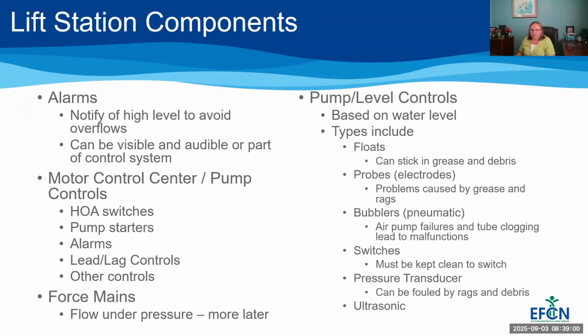And then there's pneumatic controllers or bubblers. The pneumatic controllers work by sensing the pressure required to force air bubbles out of a tube located near the bottom of the wet well. So when the wet well is full, it takes more pressure to push those bubbles all the way to the top than if the wet well is low. I guess we don't really have empty wet wells, but when the levels get low. So you have a set point for the pumps based on the pressure.